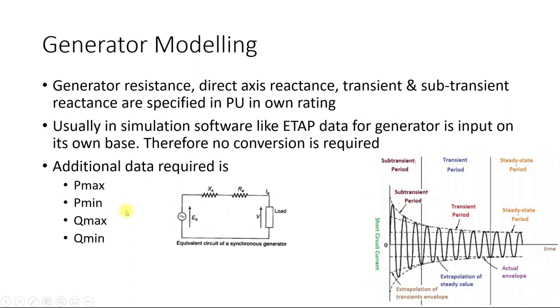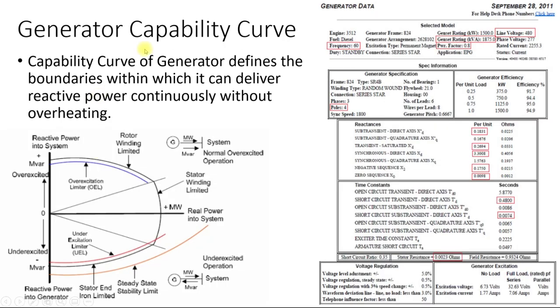You need to define the range in which the generator can change its output by providing the two extremes. Similarly, we need the voltage source information — specifically, the generator reactive capability limit — because reactive power is directly proportional to voltage. When we change the voltage, we are trying to change the reactive power of the generator. So we need to provide the values of Qmax and Qmin so that the generator can change its voltage within this range, which is given in the form of a generator capability curve.